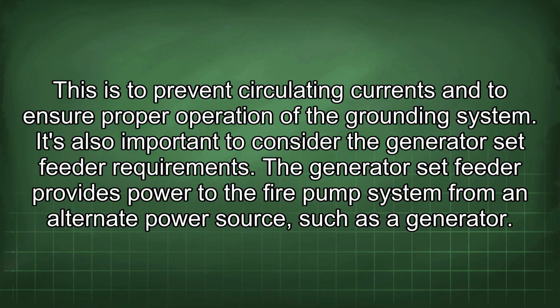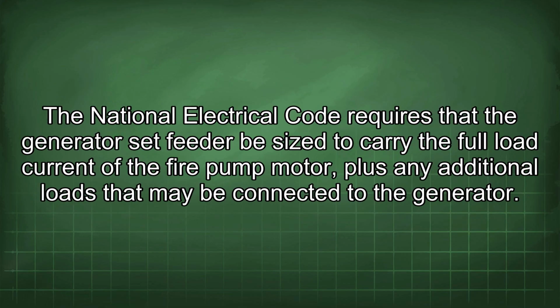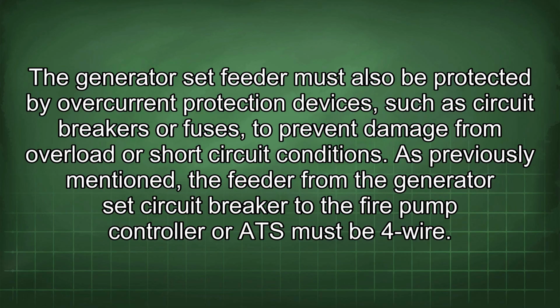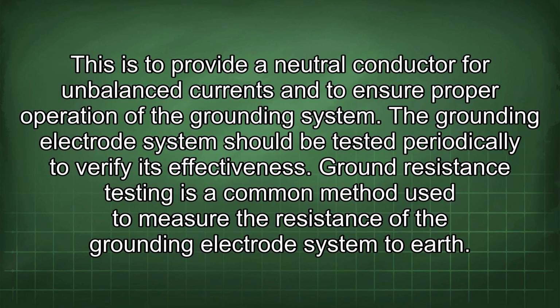It's also important to consider the generator set feeder requirement. The generator set feeder provides power to the fire pump system from an alternate power source, such as a generator. The National Electrical Code requires that the generator set feeder be sized to carry the full load current of the fire pump motor, plus any additional loads that may be connected to the generator. The generator set feeder must also be protected by overcurrent protection devices such as circuit breakers or fuses to prevent damage from overload or short circuit conditions. As previously mentioned, the feeder from the generator set circuit breaker to the fire pump controller or ATS must be four-wire. This is to provide a neutral conductor for unbalanced currents and to ensure proper operation of the grounding system.